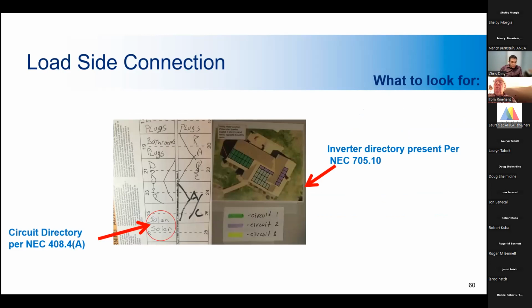All right, and once again, we see requirements for circuit identification. On the right side here, we see a good example of a directory, for a microinverter system that includes a color-coded map to tell which arrays go to which circuit. And then this specifically shows which modules are in which circuit, and that helps for easy maintenance and troubleshooting later on. And here you have a kind of a list directory, which is on every electrical panel in existence. And it's supposed to be filled out. Many times it's not, but you should make sure that it is, because that's important for future maintenance and making sure that everything is labeled and people working on it in the future know what they're looking for.